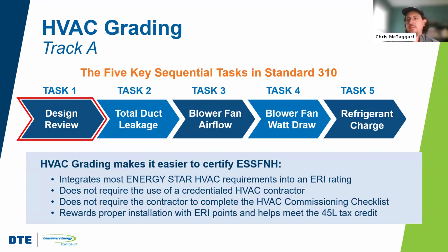I'll just say, you may think this is kind of like a no-brainer thing. Shouldn't this happen on every single home? Well, technically, yes, it should. Homes built to the Michigan 2015 code are required to have equipment that is designed by a load calculation and system selection through ACCA Manual J and S. So yeah, this shouldn't be a big deal, but let's just say the implementation of that is not necessarily uniform. So for that reason, Energy Star does have this more specific design and review process to ensure that it's actually being done. So we start with the design review and then move to, assuming that that is correct, the equipment was designed appropriately for the home.